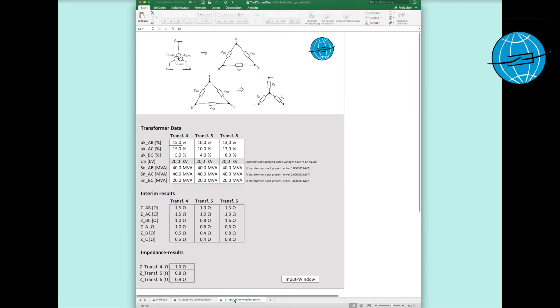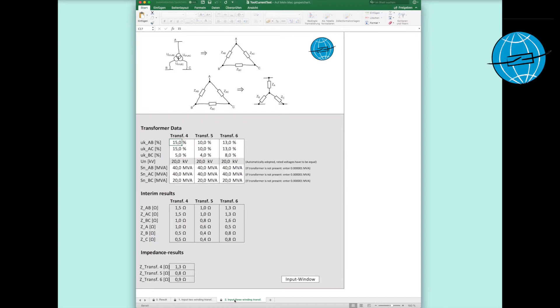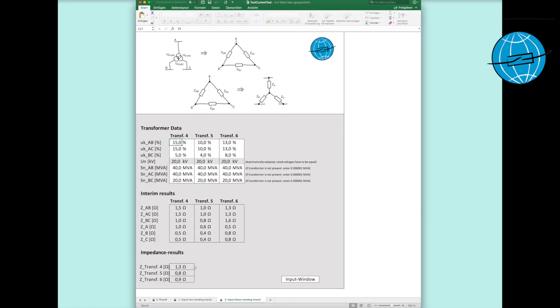On the third sheet, the same game for the three-winder transformers takes place. Here, we enter again the short circuit voltages and rated powers and receive a replacement short circuit impedance for every three-winder. Very important! The triangle to star conversion must not take place after the classical conversion from the drive technology. It has to be carried out specially for transformers. Of course, we have the proper formulas in the background working for us.